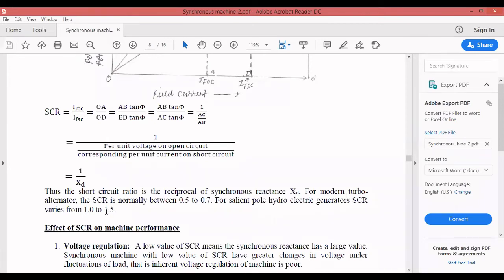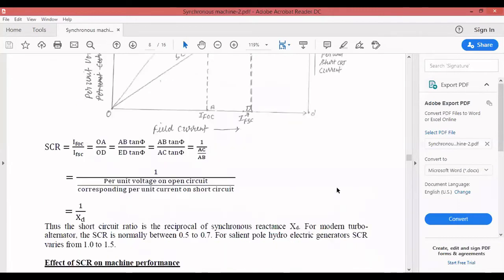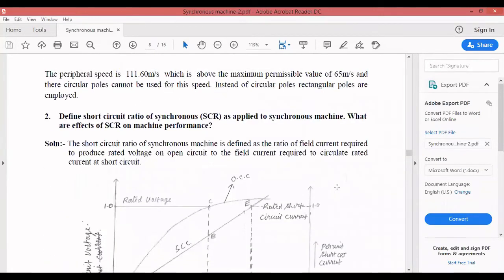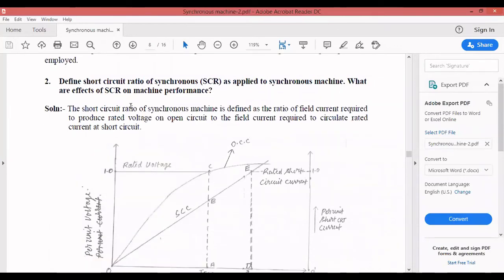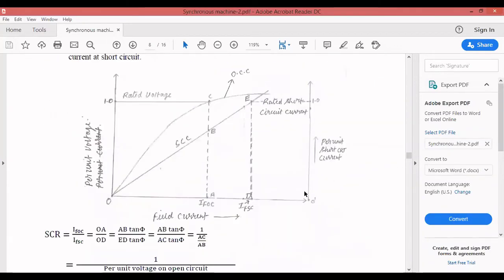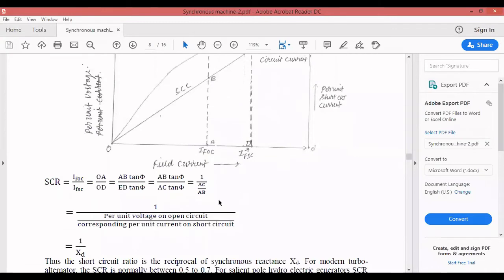For modern turbo alternators, SCR is normally between 0.5 and 0.7. For salient pole hydro-electric generators, SCR varies between 1 and 1.5.